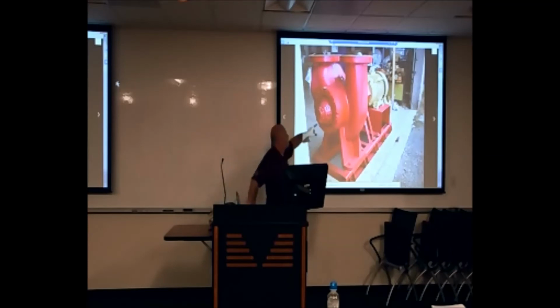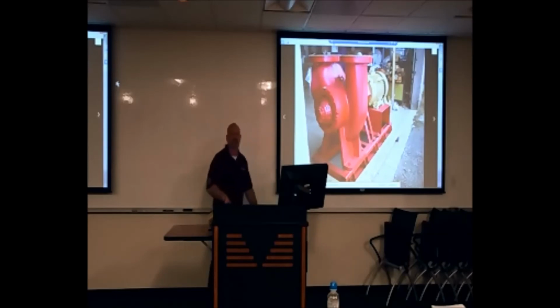Actually, this is just a vent cover. On the old style pumps, you would see the shaft sticking out in this section. Well, on ours, since it's this cap design and we no longer have the shaft exposed, we cover it up underneath there. It's just a very short section of that shaft. We tried to shorten the shaft on these as much as possible to have the least amount of deflection or flexing of that shaft. So we shorten the shaft, put the bearings closer together so there's less movement of that impeller inside there, because it does move a lot. I'm amazed. Big, thick 2-inch shaft going through this thing, and in testing you can see that shaft actually flexing a bit.